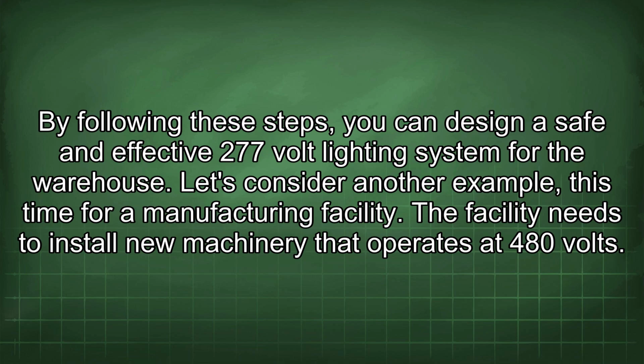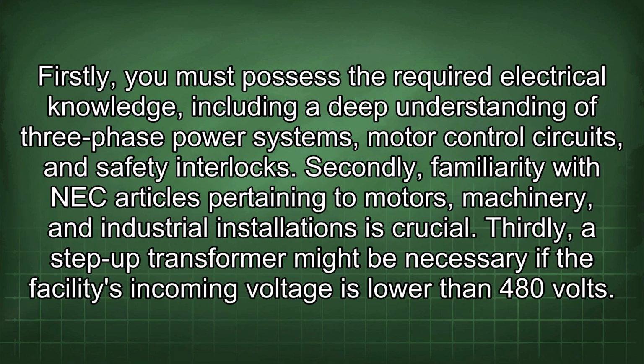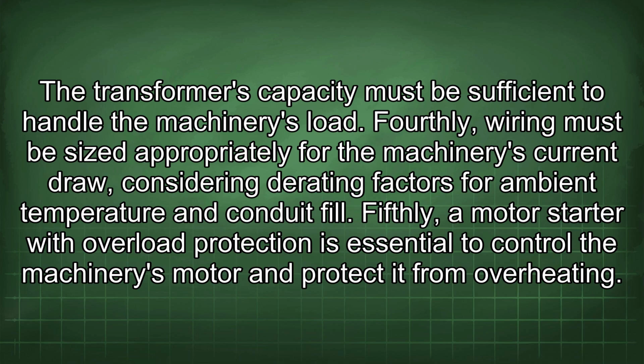The facility needs to install new machinery that operates at 480 volts. Firstly, you must possess the required electrical knowledge, including a deep understanding of three-phase power systems, motor control circuits, and safety interlocks. Secondly, familiarity with NEC articles pertaining to motors, machinery, and industrial installations is crucial. Thirdly, a step-up transformer might be necessary if the facility's incoming voltage is lower than 480 volts. The transformer's capacity must be sufficient to handle the machinery's load.